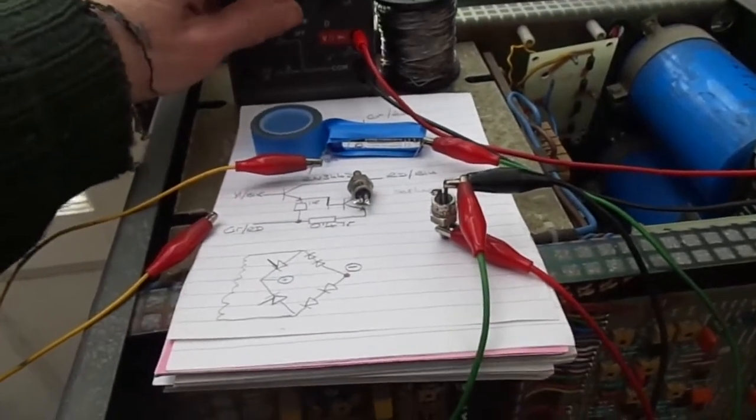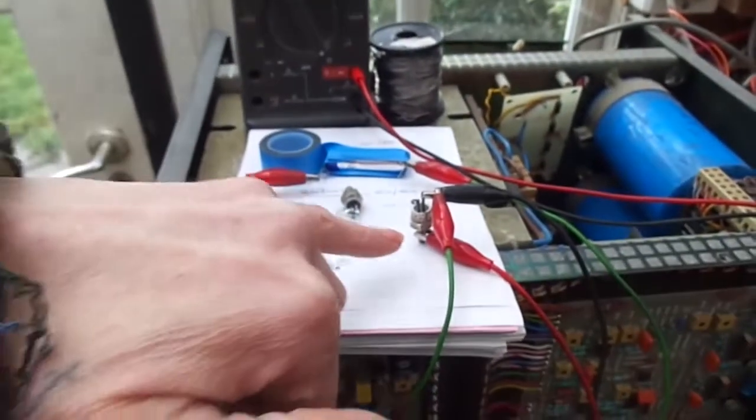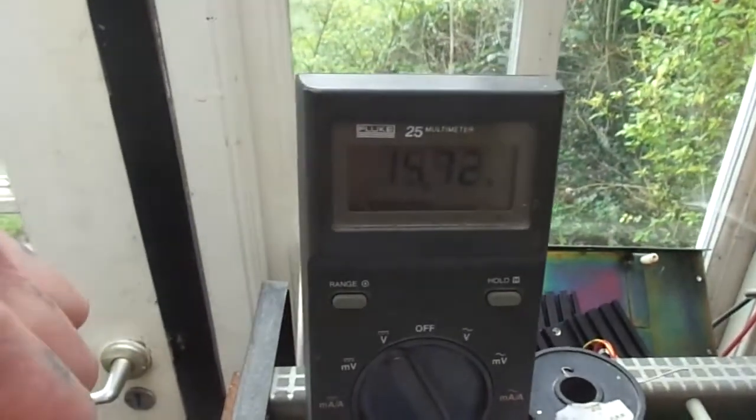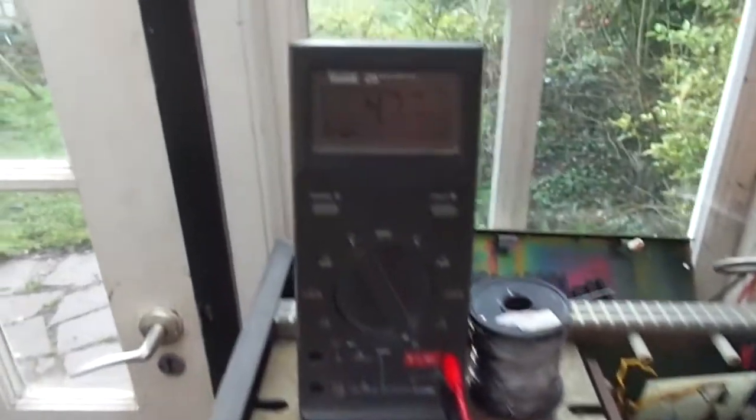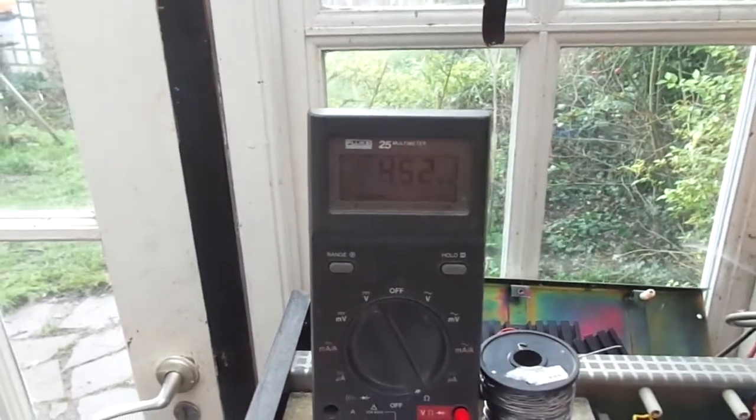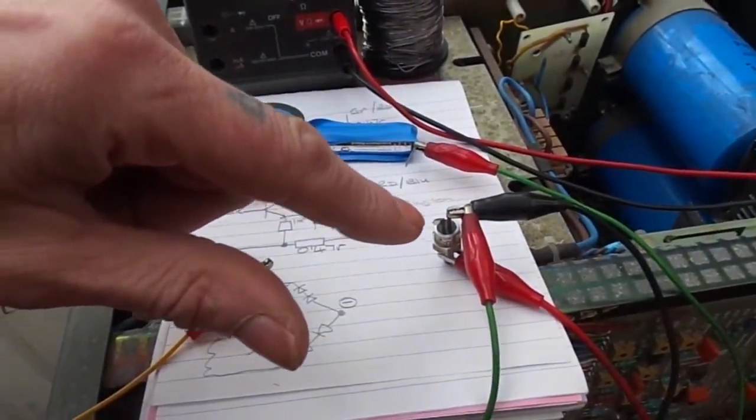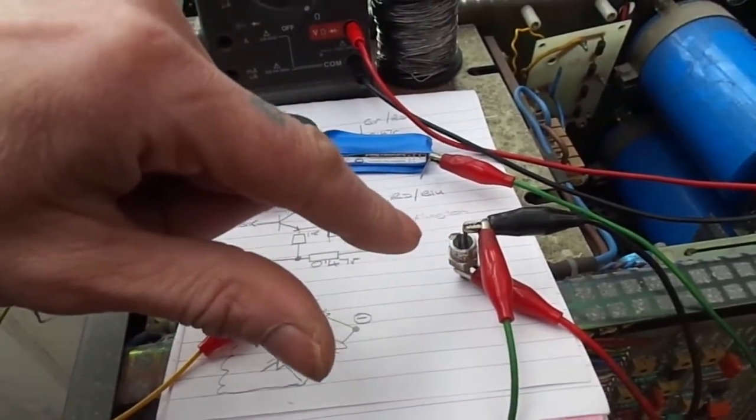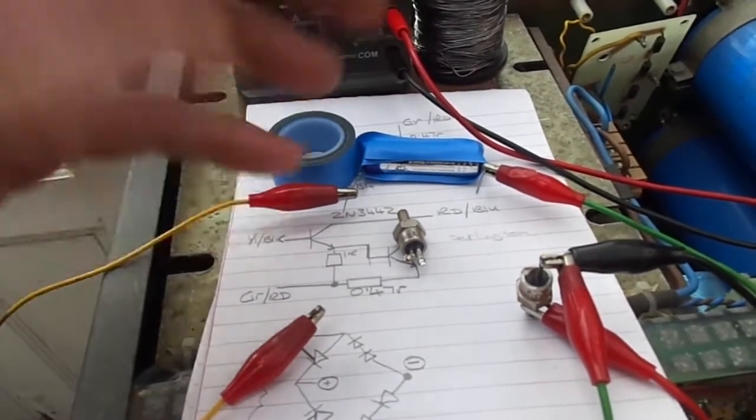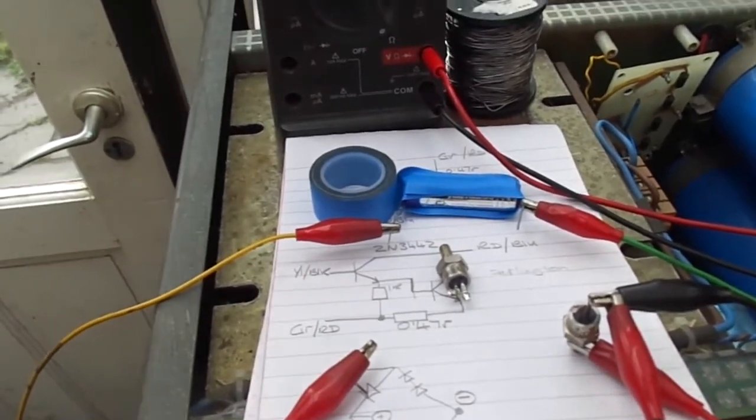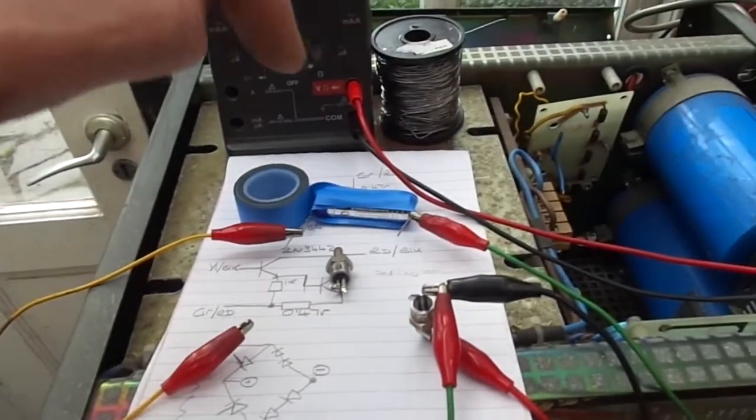So here I've got one set up to try and test it. I'm measuring from anode to cathode. As you can see, we've got 14, 16 meg. If I touch the gate, I've basically just got a battery with a resistor, just touch the gate. That falls to 4.7. Now it should stay open. But these are quite high voltage. These are CS8-12s, obsolete thyristors, 1200 volt rated, 25 amps. I was thinking I've got to replace these. You can't get them anymore. But you can get replacements for about 10 or 15 quid. They look alright. So I'm going to pop those back in.